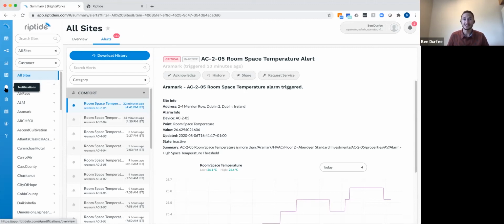We can do digest alarms for daily consumption, or escalation, so critical alarms like a chiller shutdown are actioned — and if they're not, someone else is notified, so you correct them before they become major issues on site. It allows your system to keep running optimized the way it's supposed to.